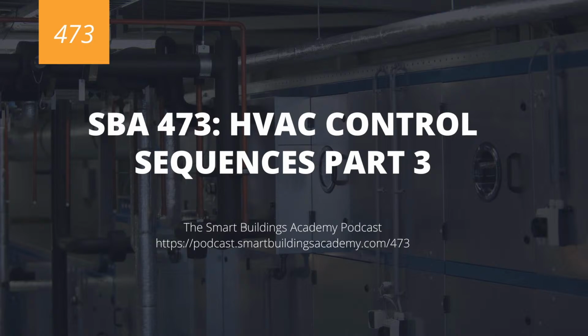And I think most folks would be better just picking a static discharge air pressure set point, especially here in the US where utility costs are so low. I know that this slightly, not doing a reset sequence, slightly increases the wear and tear on the equipment and increases the utility cost of the equipment. But here in the US, we can afford that. Overseas, maybe not so much. But I will tell you, I've seen more problems with reset sequences than I have seen with actual, what's the word I'm looking for? Static discharge air pressure set points.